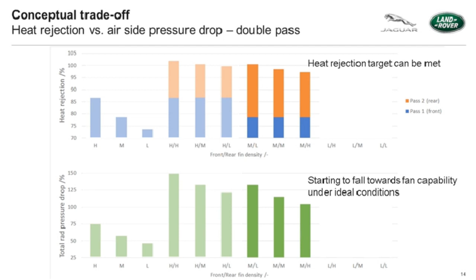Here we see that the pressure drop starts to reduce and the thermal balance starts to shift a bit, so the front pass is now doing less than 80% of the thermal duty. The final step here is to change the front pass to a low fin density radiator.